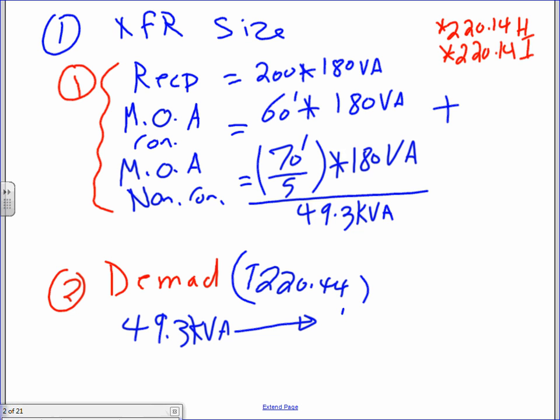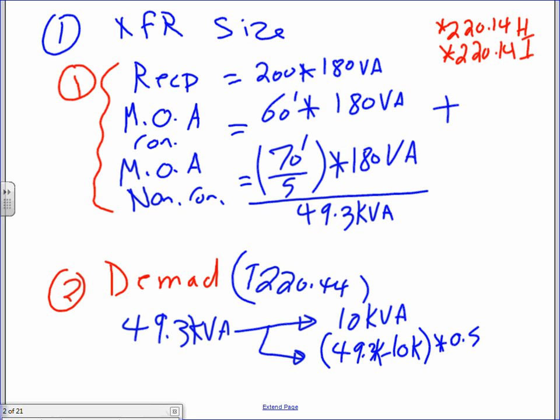The first 10 kVA, these are sacred, shall not be touched. The first 10 K, leave it alone. Anything higher than 10 kVA, which is 49.3 minus 10 K, all these are Ks, guys, remember, you will multiply by 0.5. Why 0.5? Because the code says 0.5. And then, gentlemen, you're going to add them up.